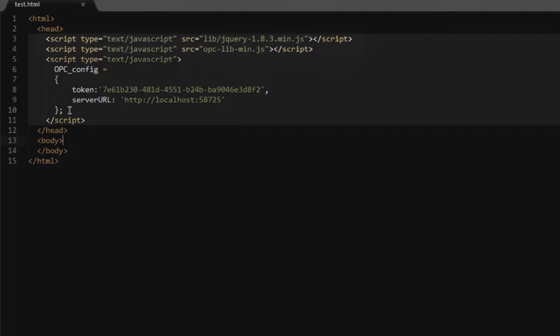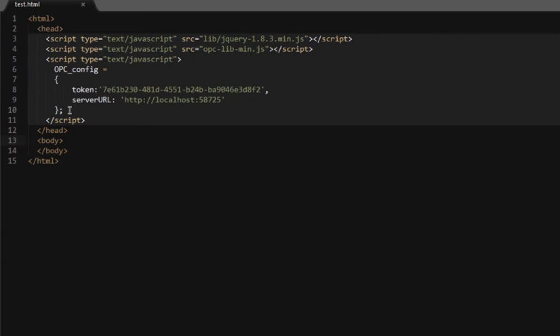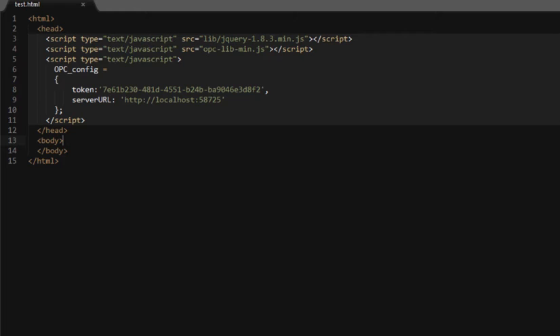I'll paste in some basic code and explain how it works. As you see, we've got two references. One is the jQuery library and the other is the opclibmin, which is the webhmi library. I've also got a piece of script with opc_config. It has a token value used for authentication. We're not going to cover authentication in this demo, but you can just put this token in there as the default. And the server URL. This is what we're pointing to for communication. Right now I've got localhost 58725 that we set up in the service control utility.